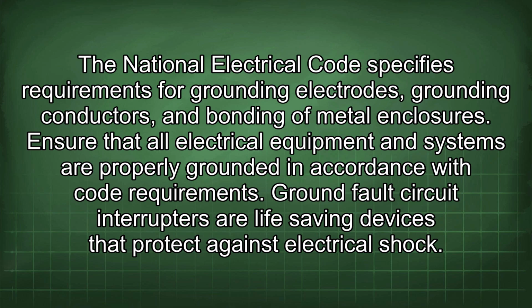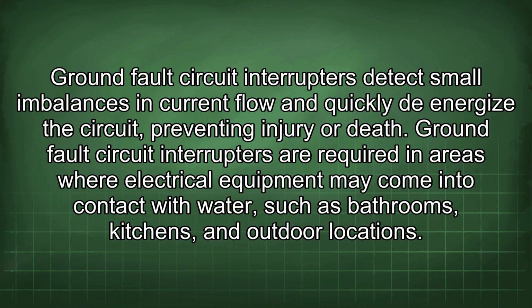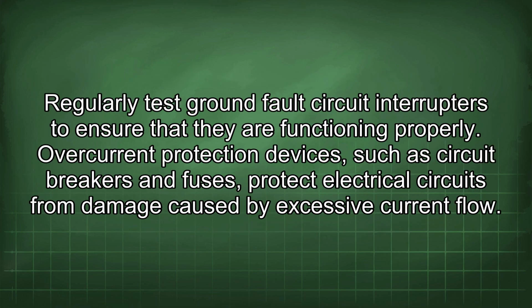Ground fault circuit interrupters are life-saving devices that protect against electrical shock. Ground fault circuit interrupters detect small imbalances in current flow and quickly de-energize the circuit, preventing injury or death. Ground fault circuit interrupters are required in areas where electrical equipment may come into contact with water, such as bathrooms, kitchens, and outdoor locations. Regularly test ground fault circuit interrupters to ensure that they are functioning properly.